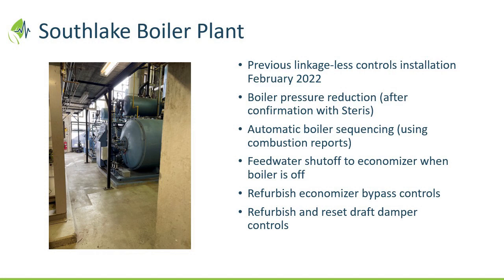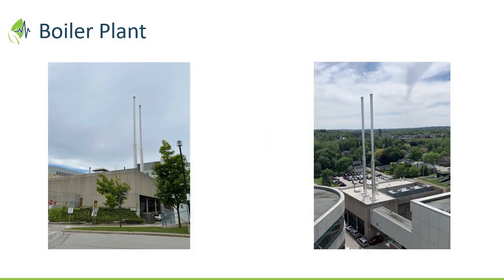So let's keep running through. Here's the boilers. You pick up what you want to talk about here, Paul. And so they're your pitches. Go for it. That's just a look at Brent's new boilers in terms of the linkageless. I don't know if Ian, you want to point out just like how the actuators, if you're not familiar with it, linkageless essentially puts direct drive on the fuel and on the air. So rather than having long linkages that can get play and slop in there, the actuator itself is directly on what measures your fuel and what measures your air. These boilers also have variable speed drives in the combustion air. So, Brent's running potentially half the capacity of that boiler with a 20 horsepower motor. Why run that all year round when you can cut that in half and then control combustion a little tighter because of it.